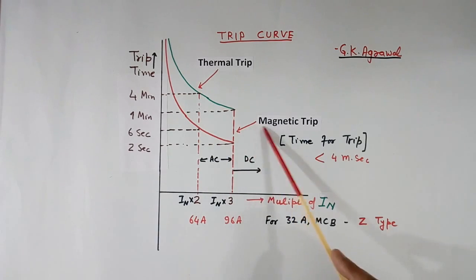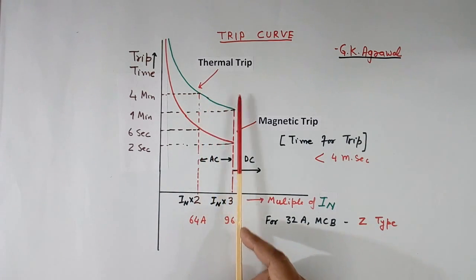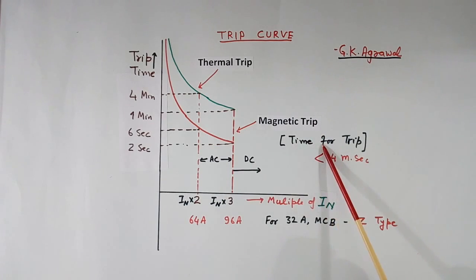This line is for magnetic trip. Whenever current exceeds more than this or more this, anything between 2 to 3 times, this line can be anywhere, the breaker will trip and the trip time will be very fast. It will be very low, 4 ms or less. This I have taken for a Z-type MCB of one typical MCB. What is Z-type? I will tell later.